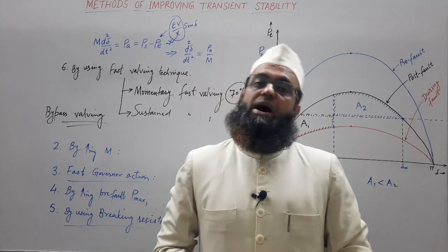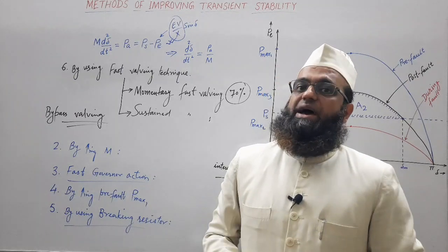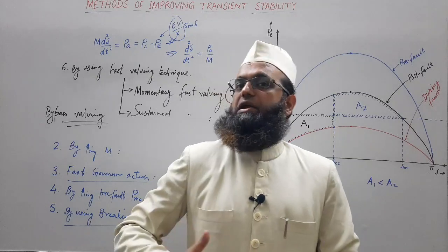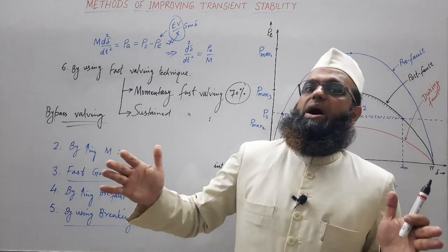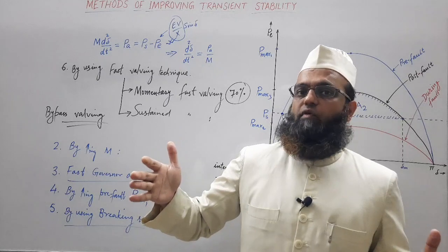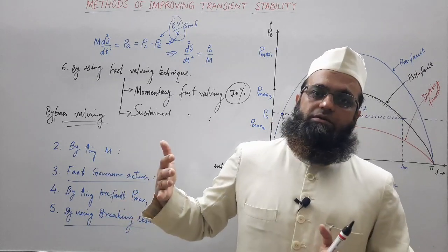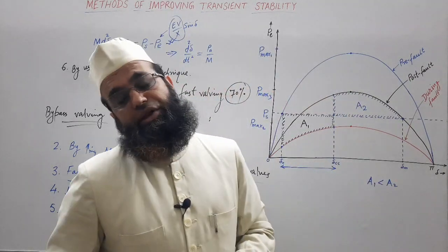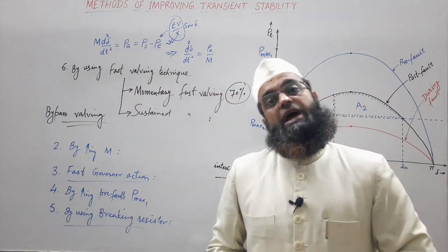we have one bypass valve, and as soon as a fault occurs, the steam is bypassed, directly sent to the condenser, if we have a sufficient bypass system to provide that extra capacity for bypassing the steam to the condenser, having a large amount of energy. So that energy is again extracted with the help of feed water.